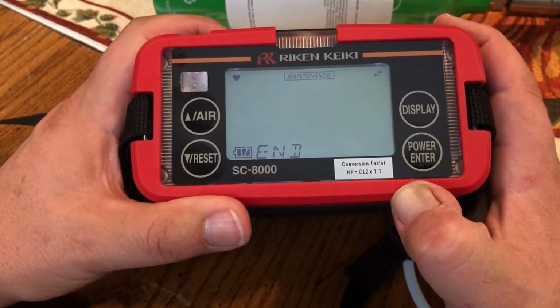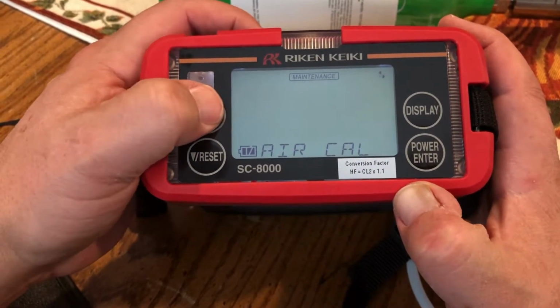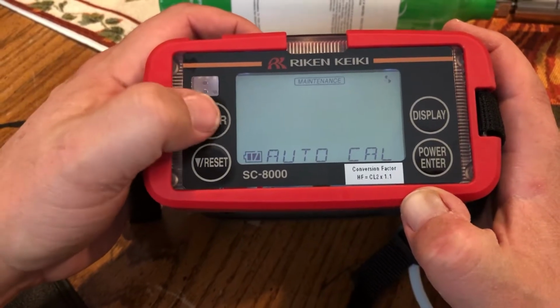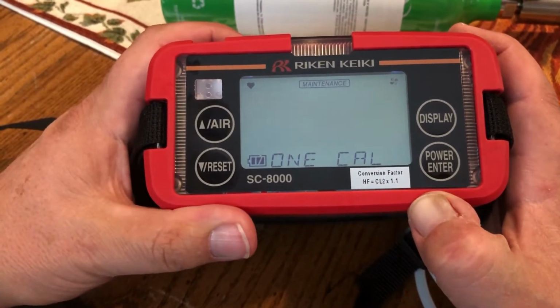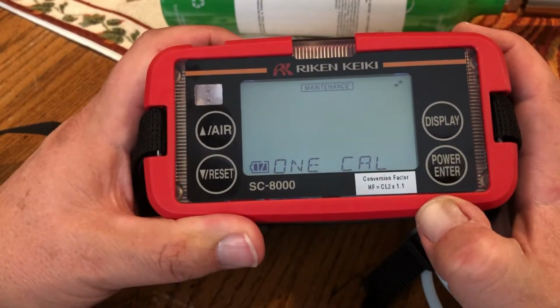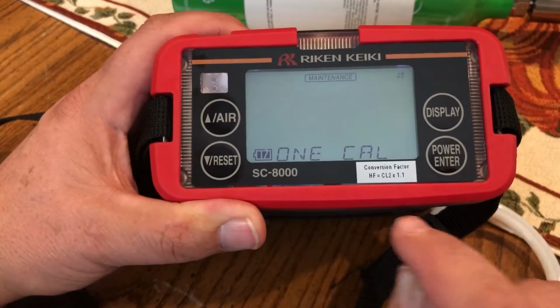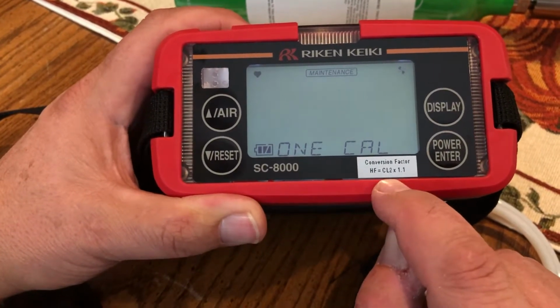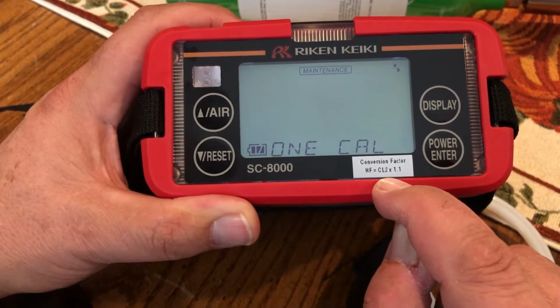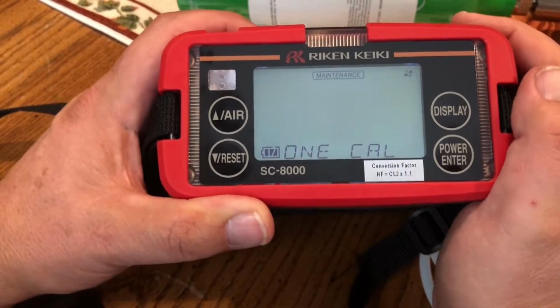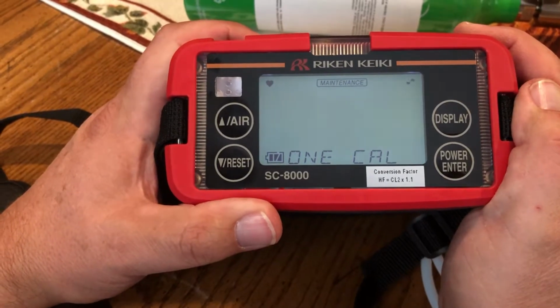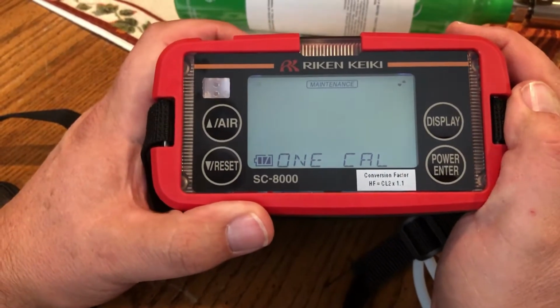At this point, you use your up arrow key. You will see auto cal by pressing once. Go ahead and hit it again and go to 1 cal for an individual calibration of the HF sensor. Notice here we have a conversion factor listed, HF equals CL2 times 1.1. That math tells us that we are looking for a span value of 2.2 ppm.